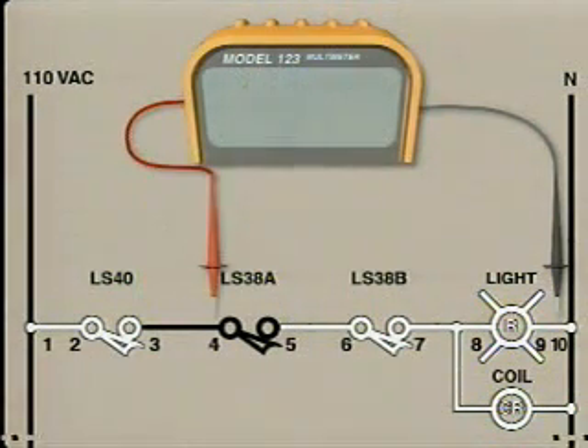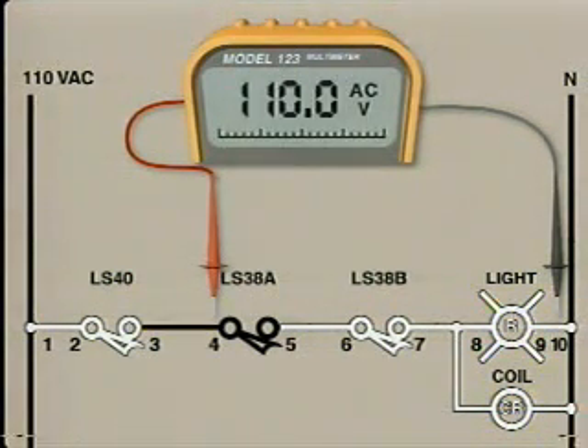The electrician splits the remaining portion of the circuit in half by checking test point 4. This check will tell him if the connection between test point 3 and test point 4 is good. At test point 4, the electrician reads full line voltage.